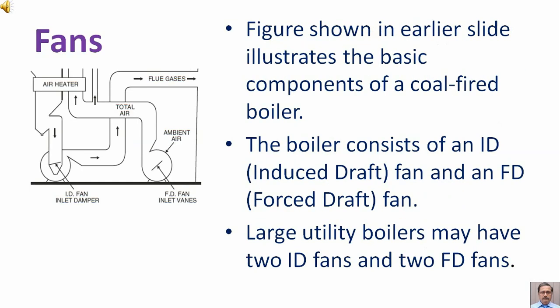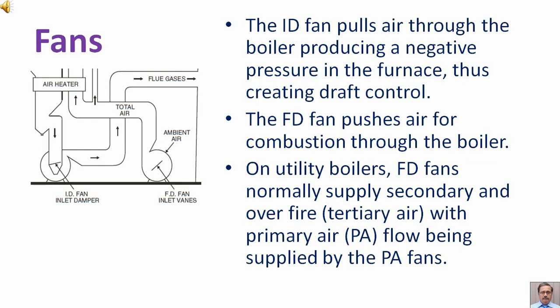The figure shown in the earlier slide illustrates the basic components of a coal-fired boiler. The boiler consists of an ID (induced draft) fan and an FD (forced draft) fan. Large utility boilers may have two ID fans and two FD fans. The ID fan pulls air through the boiler producing a negative pressure in the furnace, thus creating draft control. The FD fan pushes air for combustion through the boiler.